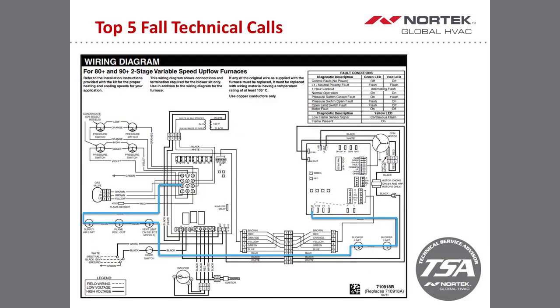So the next wiring diagram that we have here is the 2-stage equipment. The limit circuit on the furnace is kind of split up between the blower board and your main board. Now, a question that we get on this is, what's the easiest way to jump out the limit circuit for testing? Maybe if we're having an intermittent issue that we need to track down, or if we have an issue with maybe a high ohm value or a grounded limit circuit.